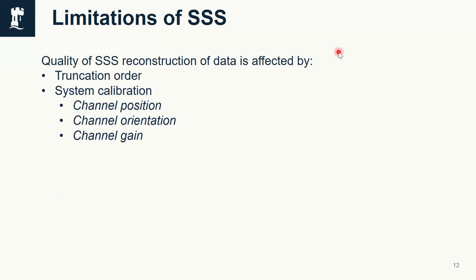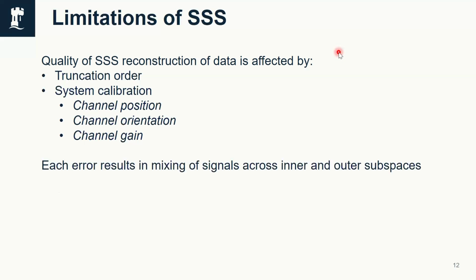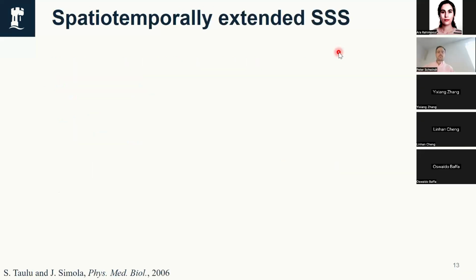It's also really crucial that we have accurate system calibration. So what we mean by system calibration in MEG, of course, is the channel position, the channel orientation, and the channel gain. We need to know those really well in order to make sure that our data are modeled properly. And each of these errors results in mixing across the inner and outer subspaces.